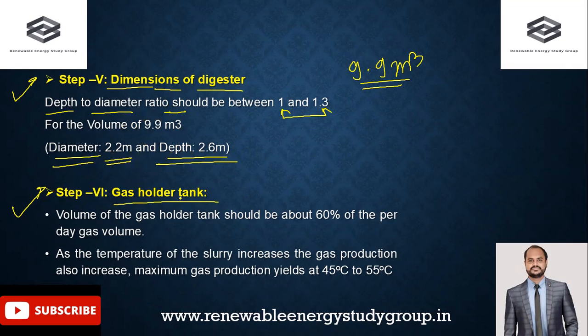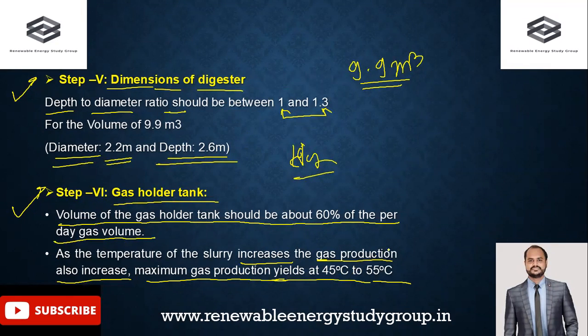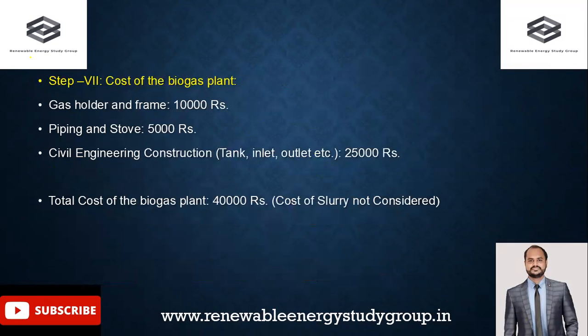Step 6 addresses the gas holder tank. The gas holder volume should be about 60% of the daily gas volume, for either a floating dome or fixed dome type. As the temperature of the slurry increases, gas production also increases. Maximum gas production occurs at 45°C to 55°C, which is the ideal temperature range for biogas generation in the digester.